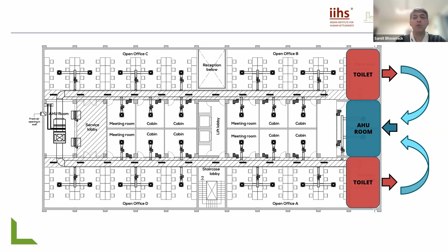Of course, while locating the air handling unit or outdoor air intakes, you also need to make sure there are no polluting sources outside the building, so you need to be aware of what's outside. But once you've done that, you want to make sure you don't short cycle the exhaust from the building back into the same air handling unit.